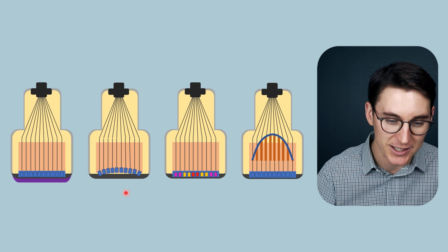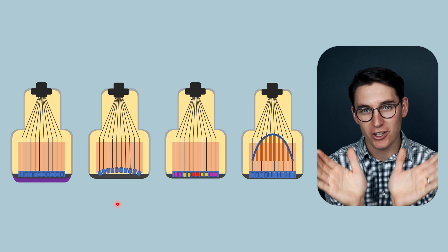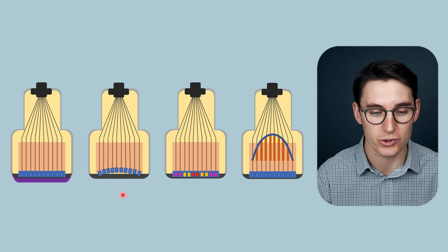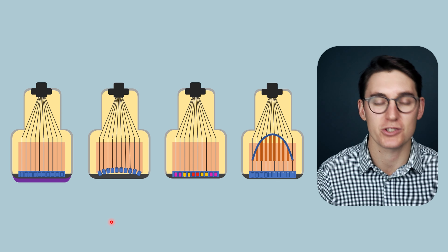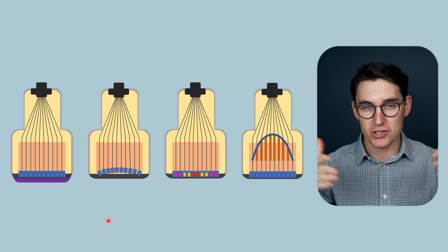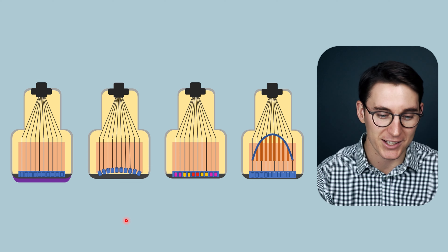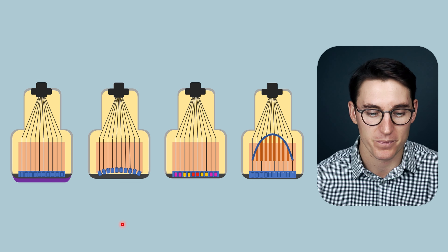The second mechanism is to use a curved transducer array. The curved shape of these transducer elements will focus the ultrasound beam again to a set focal depth.